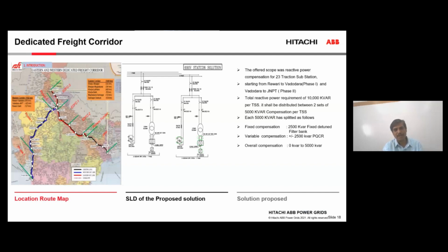In both these places, we are giving a combination of the dynamic power compensator DRPC, combined with capacitor-based harmonic filters. This hybrid system is the most optimal system, maintaining a power factor of 0.95 and above, and it is also expected to clear the harmonics. This way it will save a lot on electricity bills for the operators, and at the same time the rail will have very good power quality that will help the equipment themselves and also the system.